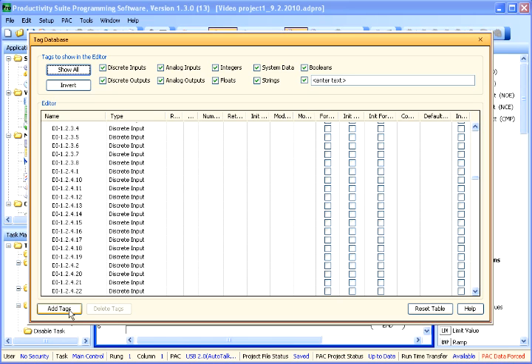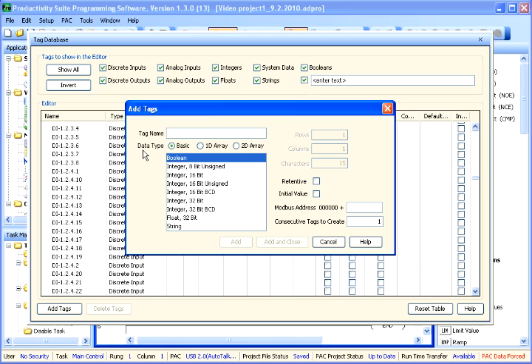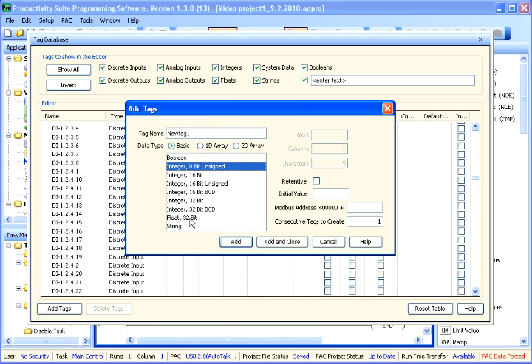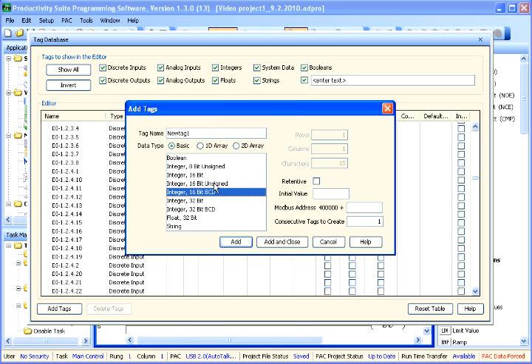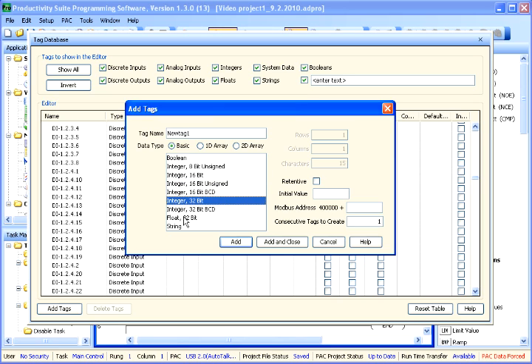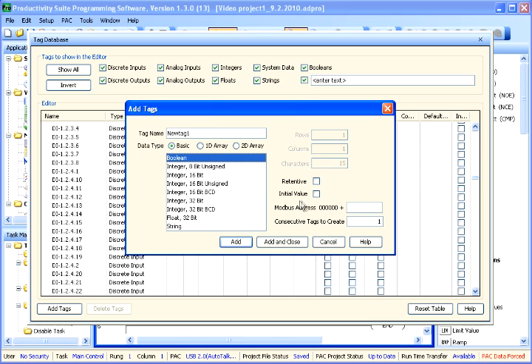If you want to add a tag, you simply add tag, type in the tag name, identify whether you're looking for a Boolean, an integer, floating point, string, whether you're looking for a 1D array or a 2D array. There are quite a few data types available. If the integer needs to be 16-bit, signed, unsigned, 32-bit, float or string, we will just create a Boolean tag. And you can also select at this point whether you want it to be retentive or have an initial value. You can also assign a Modbus address, and if you want to create multiple addresses, you can start off with a new tag with a number value at the end if you want to create 50 consecutive tags.